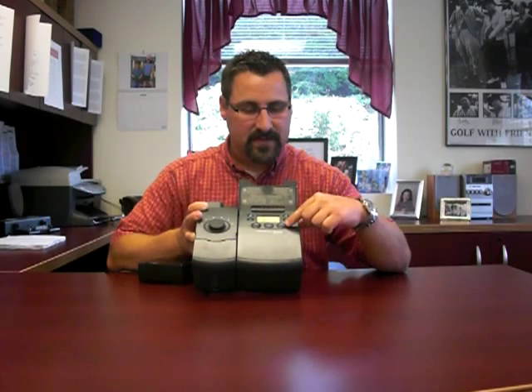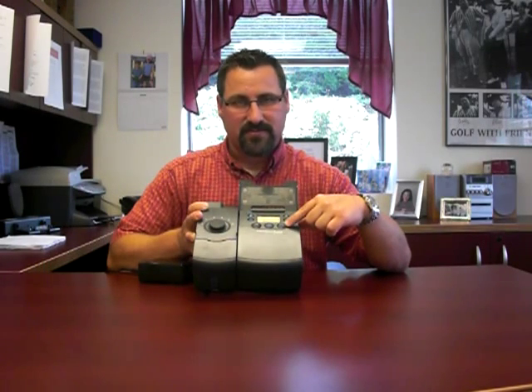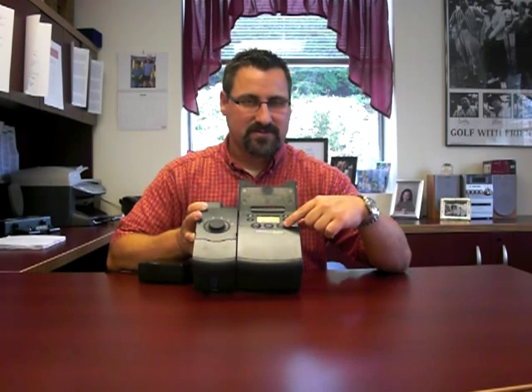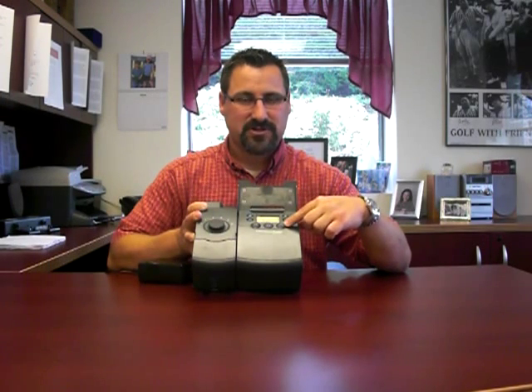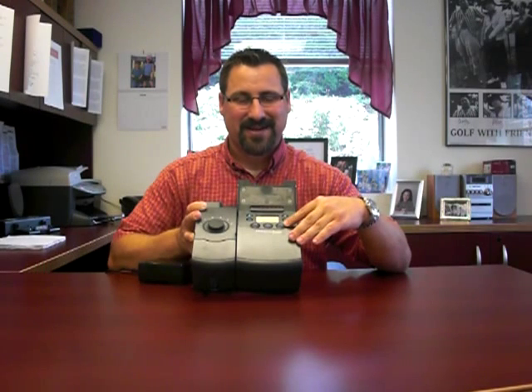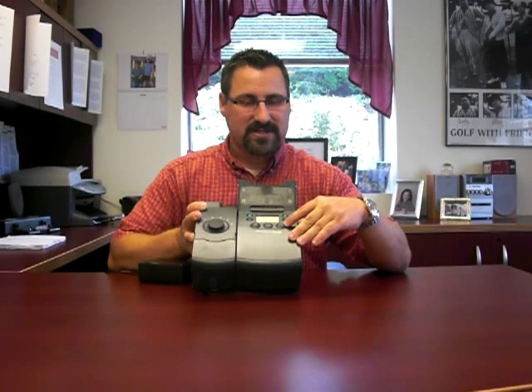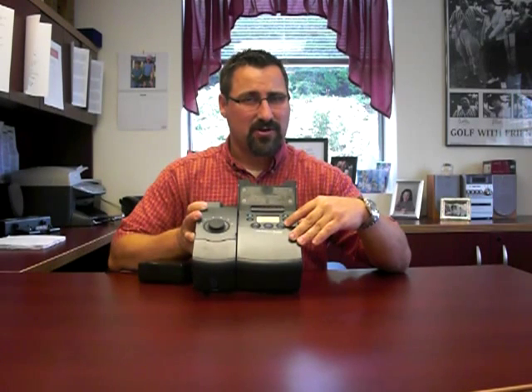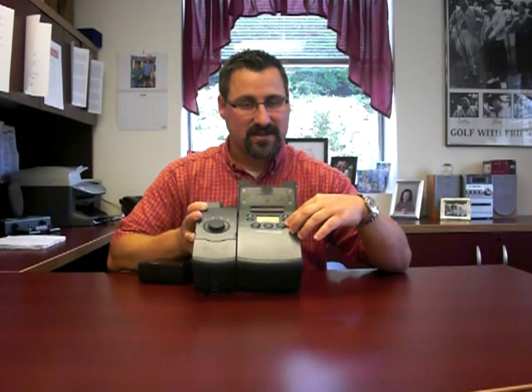The other button on the front that's lit up in blue says C-Flex. This is a button that we're going to have set for you, so you're not necessarily going to have to hit this button every night. What C-Flex does is every time you breathe out, the machine senses that you're trying to exhale, and it actually lowers the pressure a little bit right when you first start to breathe out, so it gives you a break. Breathing out can be a tricky part of the CPAP therapy to get used to, so when you exhale, if the machine gives you a little break, it's usually a lot more comfortable. That's what the C-Flex does.